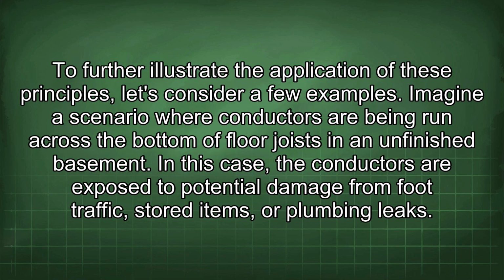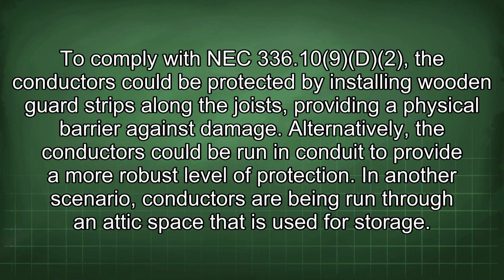To further illustrate the application of these principles, let's consider a few examples. Imagine a scenario where conductors are being run across the bottom of floor joists in an unfinished basement. In this case, the conductors are exposed to potential damage from foot traffic, stored items, or plumbing leaks. To comply with NEC 336.10 D2, the conductors could be protected by installing wooden guard strips along the joists, providing a physical barrier against damage. Alternatively, the conductors could be run in conduit to provide a more robust level of protection.